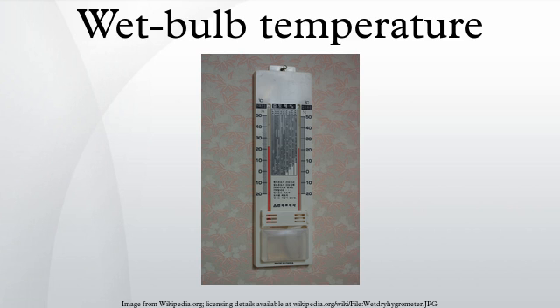At relative humidities below 100%, water evaporates from the bulb which cools the bulb below ambient temperature. To determine relative humidity, ambient temperature is measured using an ordinary thermometer, better known in this context as a dry bulb thermometer. At any given ambient temperature, less relative humidity results in a greater difference between the dry bulb and wet bulb temperatures — the wet bulb is colder. The precise relative humidity is determined by reading from a psychrometric chart of wet bulb versus dry bulb temperatures, or by calculation.